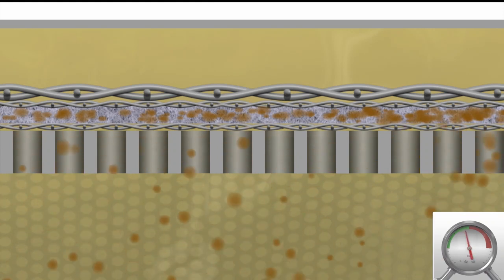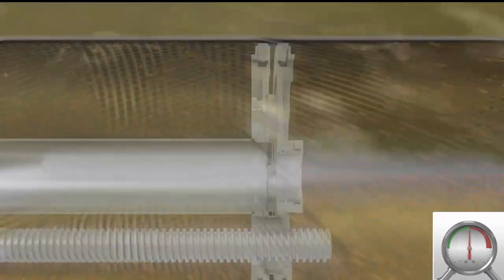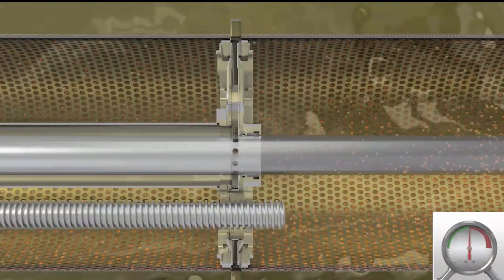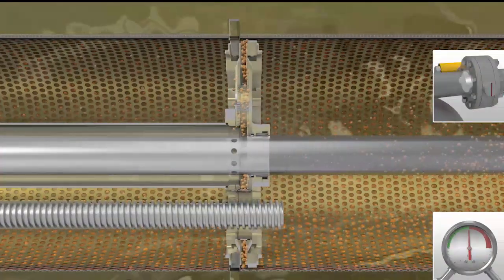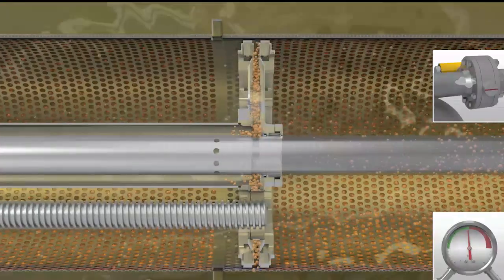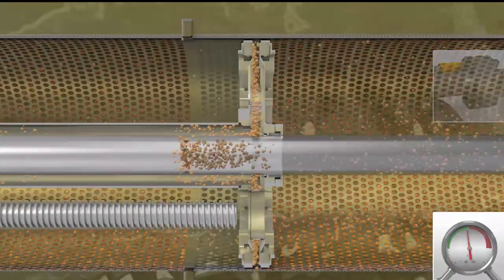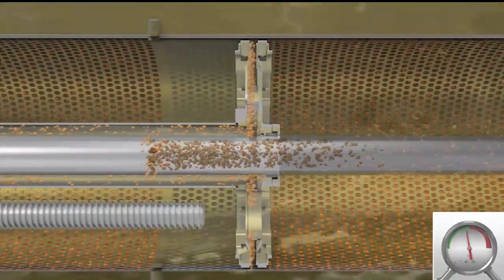Particles gradually blocking the pores of the filter material increase the differential pressure. Upon reaching a preset rise of differential pressure or after an adjustable period of time, a backwash is initiated.